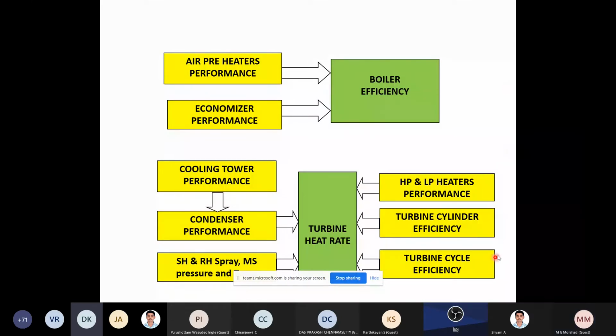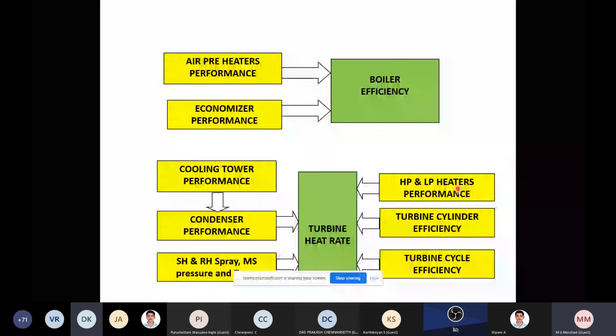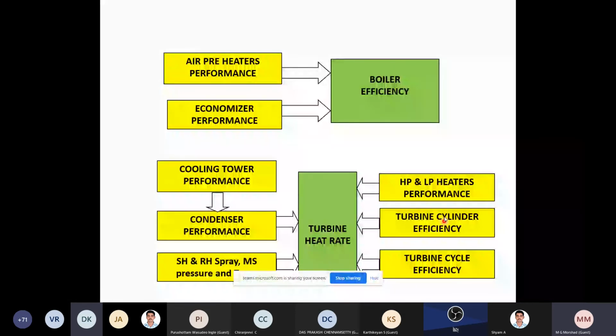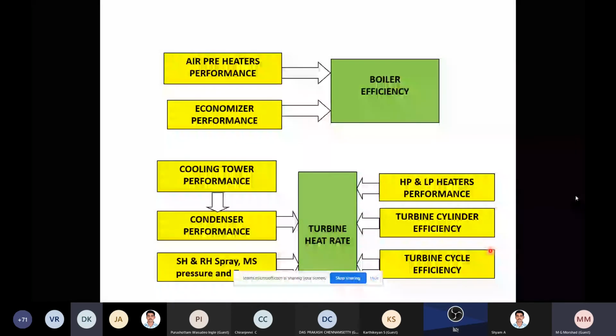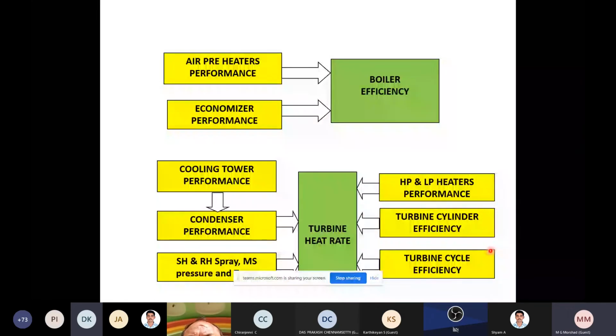Then turbine heat rate. The turbine heat rate will be calculated along with these calculations, because the turbine heat rate also depends on condenser performance, superheater and reheater spray, MS pressure, main steam pressure and temperature, then HP and LP heaters performance, turbine cylinder efficiency, and turbine efficiency. So these are all the parameters related to the turbine heat rate. So you have to prepare the scope accordingly. These are all the things you have to bring into the scope of work.